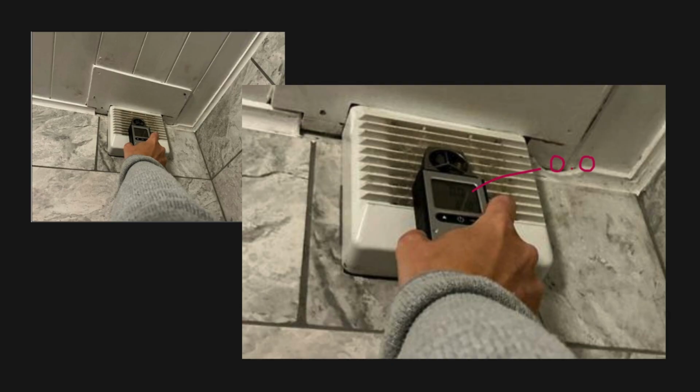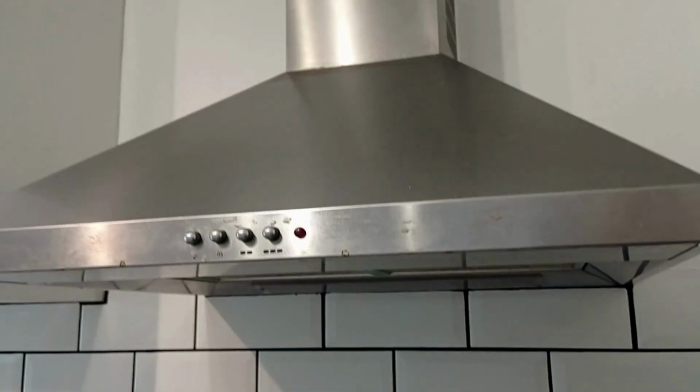So using a digital anemometer, which is the best way to check to see if a fan's working, this is just a basic one, but it will do the job that I needed. It showed that there was actually zero flow going through that fan, so it wasn't working at all. And this is an internal bathroom that doesn't have a window at all, so the fan not working, especially if no one knows it's not working, is a massive factor in terms of the increased risk for mould across all of the house, but especially the adjacent rooms.